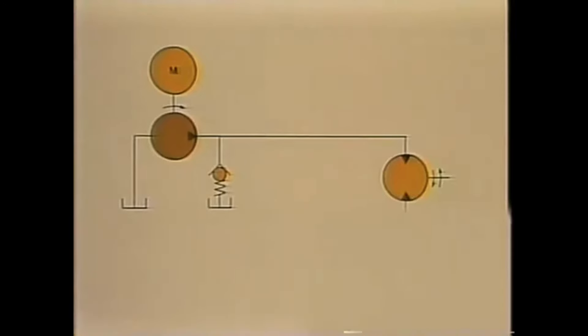Okay then, what if we direct the pump flow into this port? The opposite one. It'll rotate the motor the opposite way, right? Right. But instead of re-piping our circuit to change direction, let's just add another valve. This one, a directional valve. We'll run a line from this port to one side of the motor and from here to the other side. Now, with the pump connected into here, we can flip this handle and direct flow into either side of the motor. Of course, there will be flow out of the opposite side, which we'll pipe back to the reservoir through this, the fourth port in our directional valve.